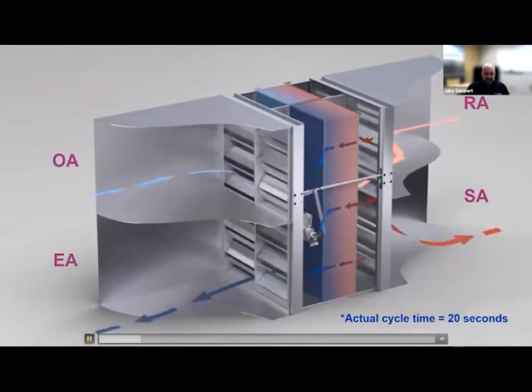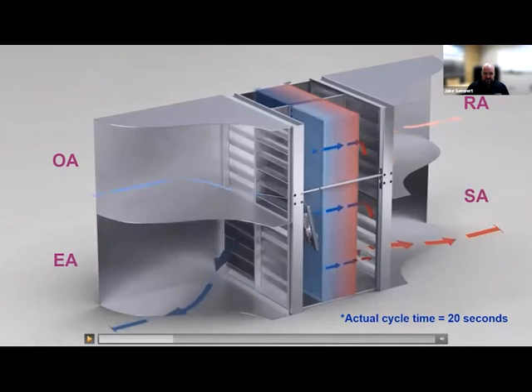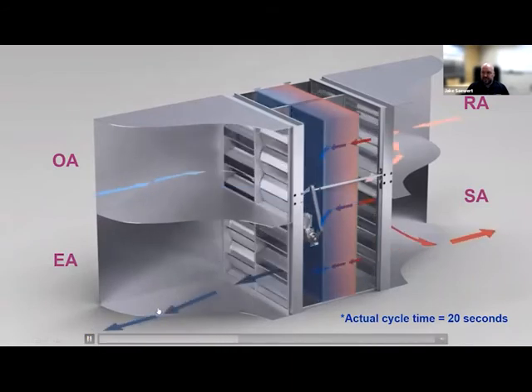And you can see once the dampers flip, now what's going to happen is the outdoor air is actually going to go through the other side of the heat exchanger. And the same thing's happening here. It's going to go through this damper. It's going to open up into the full height at a much slower velocity, and then go through the bottom here on the discharge. Return air and exhaust air do the exact same thing. It's just the opposite heat exchanger.